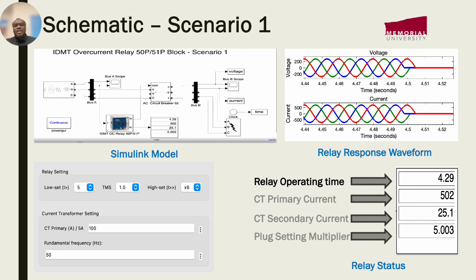performance of the relay. In doing that, we recorded a trip signal at 4.29 seconds, and this is the actual relay trip time.